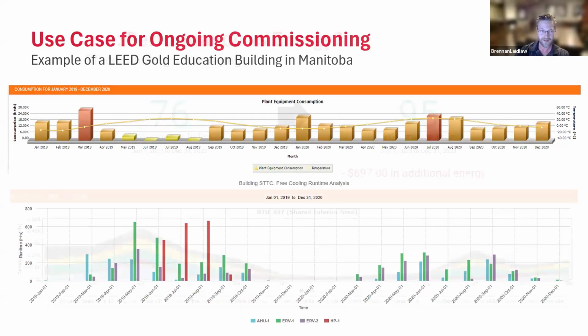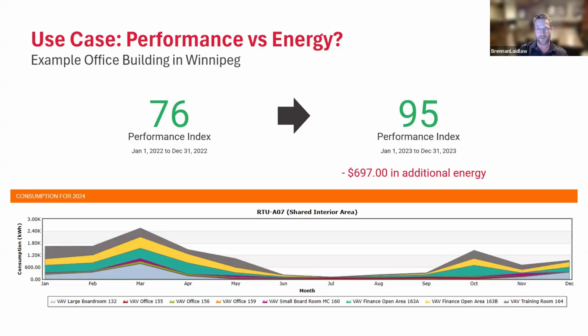The last data analytics example I've got is an office building, and their performance was doing well, like 76%, very well. But what was happening was there were a lot of cooling issues. They had a lot of big areas like training rooms and boardrooms, and these had such big cooling loads that it was forcing the office area into cooling, causing the office area to overcool. So what we did, and not most energy efficient, was we allowed the reheat coils in the ductwork, the little heaters, to turn on in the summer. So yes, a little bit of simultaneous heating and cooling just to trim a degree or two. And we found that that was able to satisfy comfort at the addition of a little bit of cost.